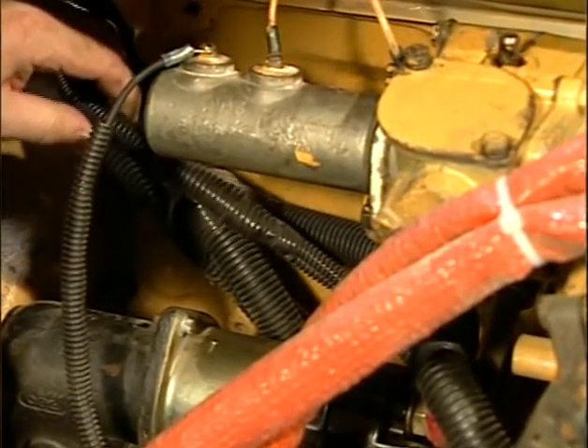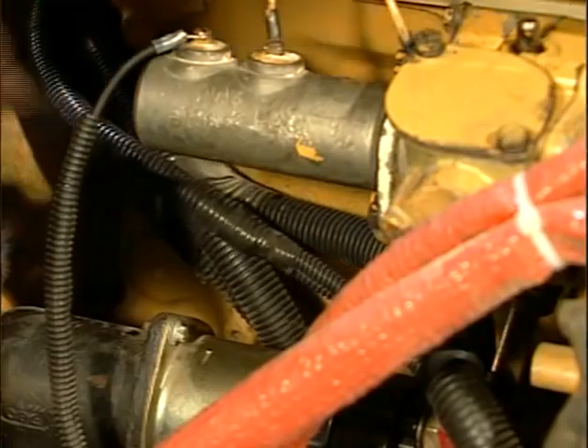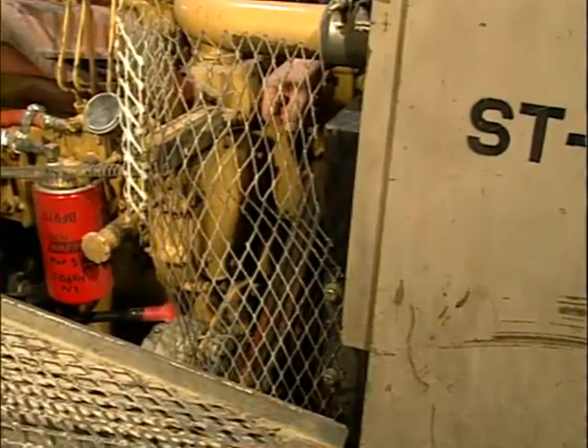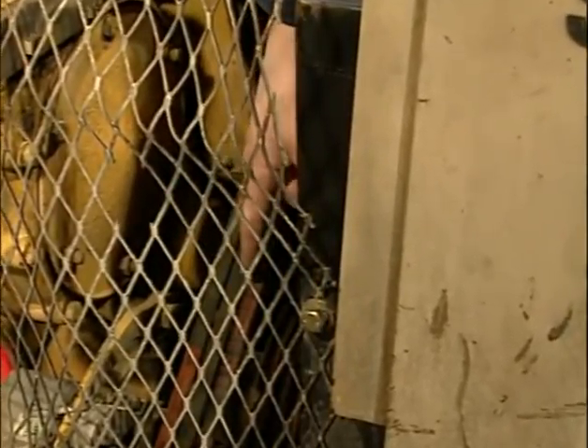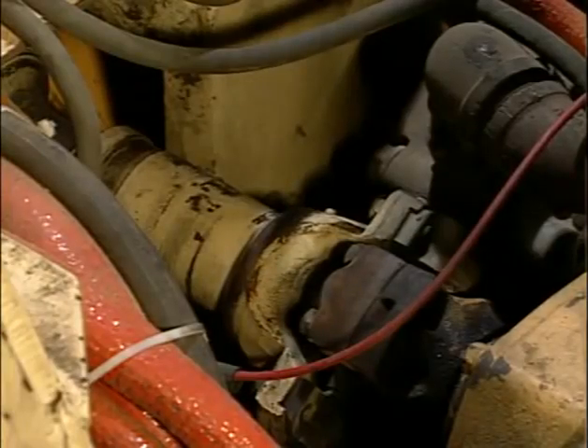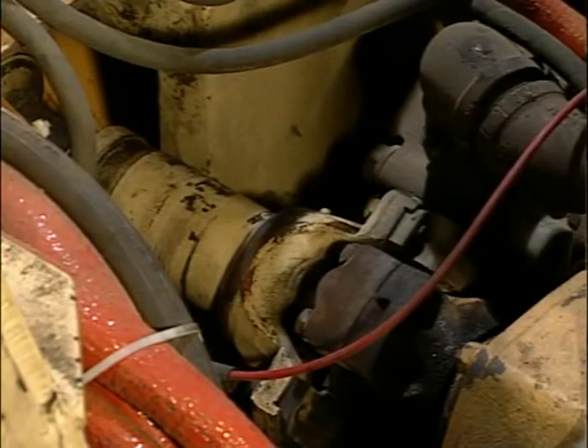Electrical wiring must have adequate mechanical protection to prevent damage to the cable. There must be adequate guarding to protect fuel, hydraulic, and electric lines when such lines pass near rotating parts such as belts. Another rotating part is the drive shaft. Should shaft failure occur, fuel lines, hydraulic lines, and electrical wiring could be damaged. Therefore, additional guarding is needed.